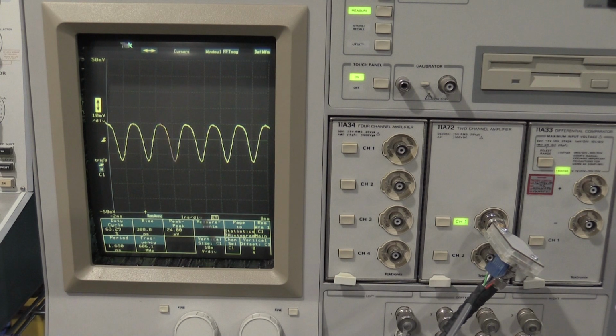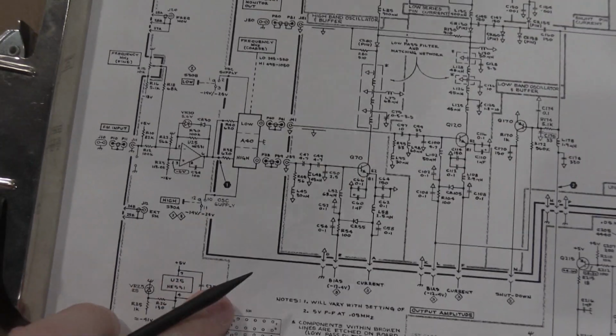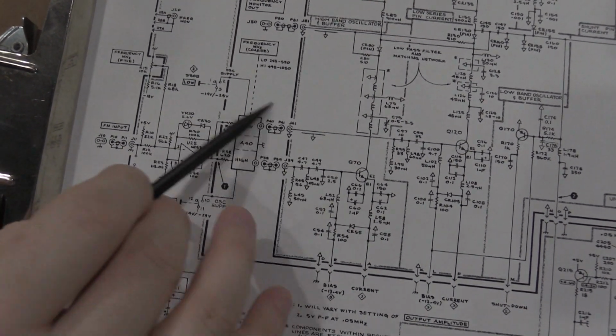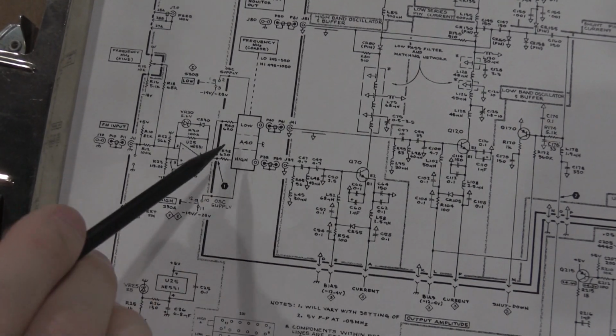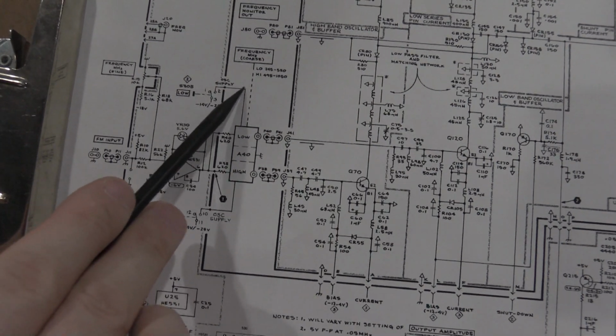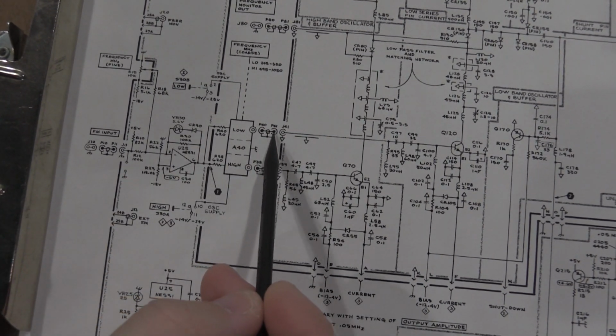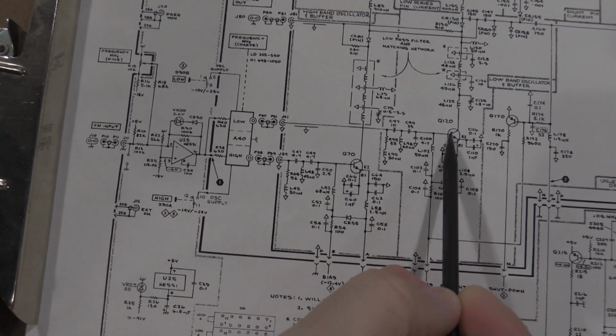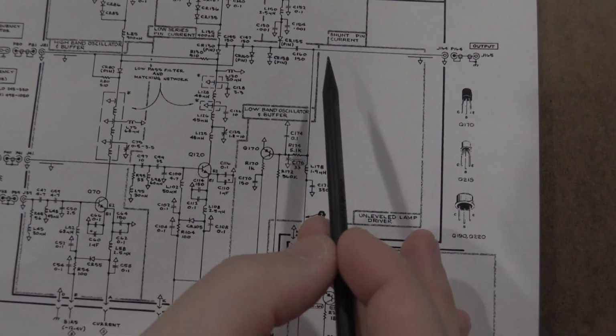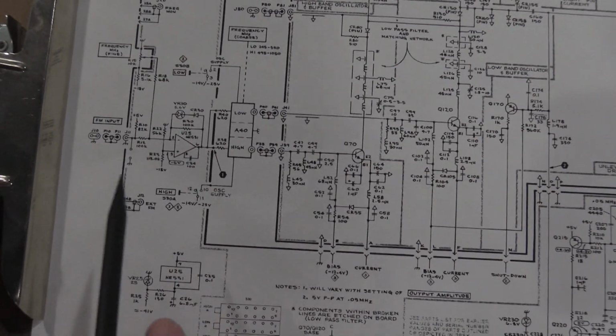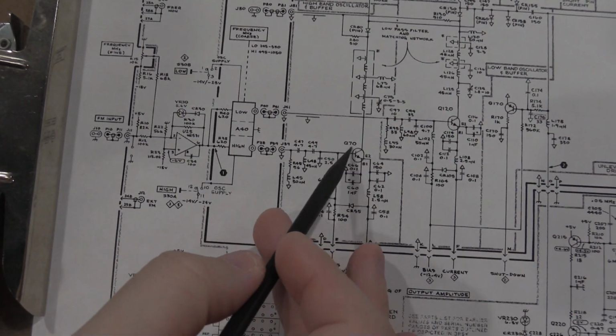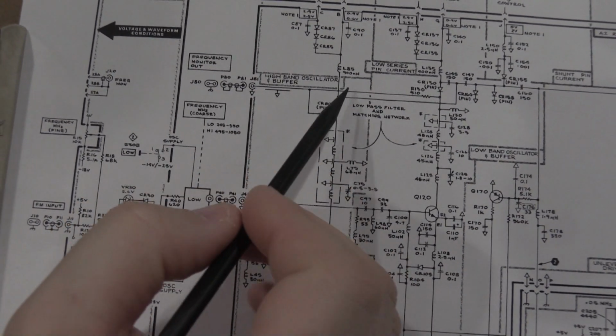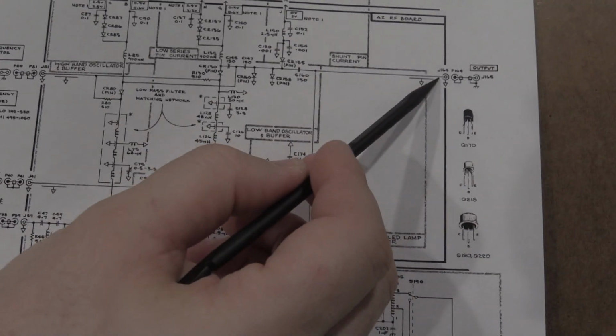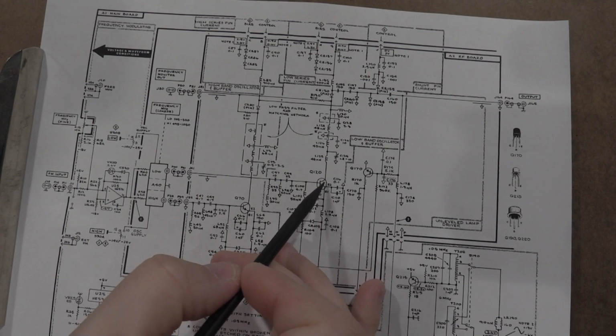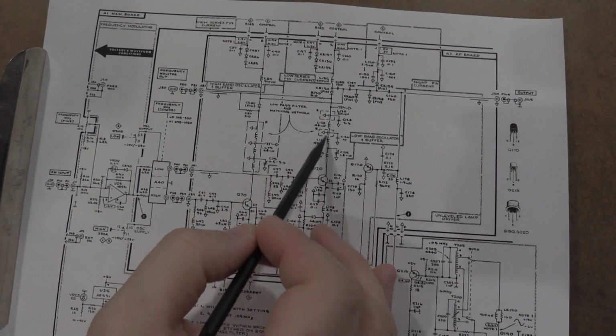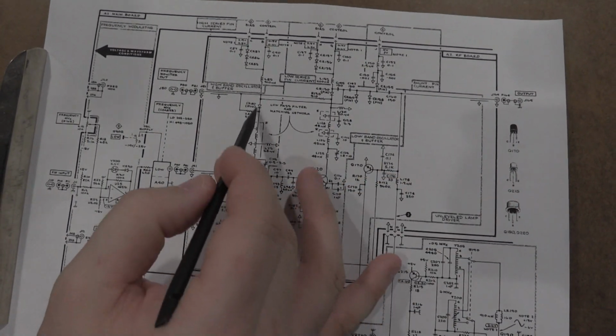Let me pull up a schematic, and we'll take a look at some points of interest. All right, so let's see. Here's the main oscillator cavity for the high and low range settings, and this is controlled by the frequency knob. The low setting comes out and comes over here to Q120, then goes into a matching network and then out to the drives for the output. On the high side, which is where we're having a problem, it comes into Q70, same matching network, and then goes out our high side over here. So we have a Q120 into an impedance matching network for the output, and then we have Q70 into an impedance matching network for the output.